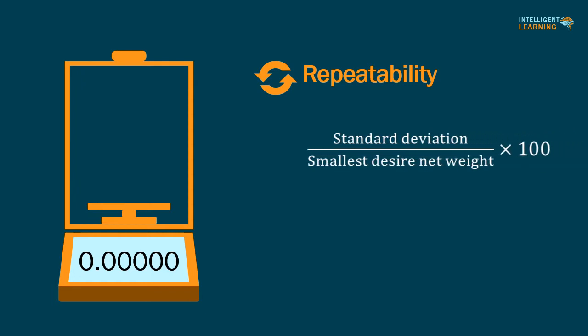Repeatability is assessed by weighing a test weight not less than 10 times. Repeatability is calculated as the standard deviation of the weighed values divided by the smallest desired net weight, and must not exceed 0.10%.